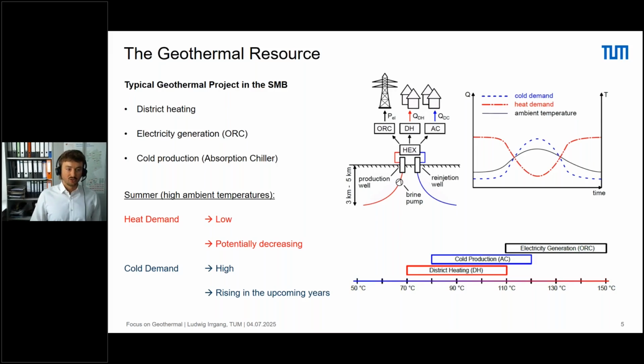Why do we have this cold production in combination with geothermal energy? As you can see on the right, depending on ambient temperatures, we have different heat and cold demands over a year's period, which means that in summer we have very low heat demand, translating to very low geothermal heat use, but high cold demand. This means we can use the geothermal heat for cooling. In contrast to heat demand, which might potentially decrease with better insulation technology, cold demand is expected to rise in the upcoming years.